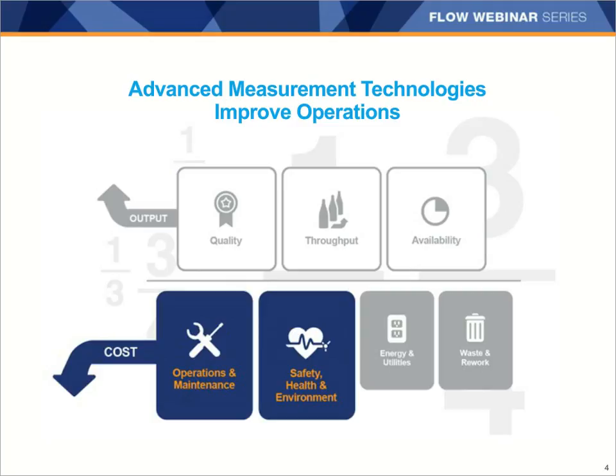The focus today, of course, is on safety, but reducing maintenance can also reduce safety risks as well. Accidents are far more likely to occur outside of normal operations, so every time you have to shut down or restart your process, you're actually introducing safety risk. So with more online diagnostics that can extend or eliminate maintenance, these safety risks are reduced.